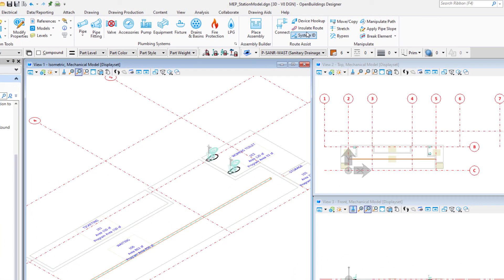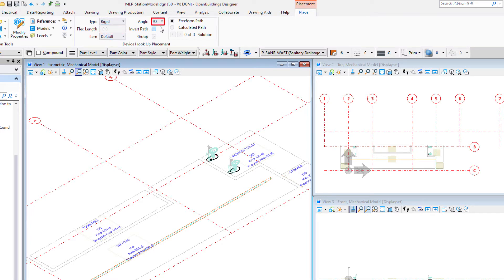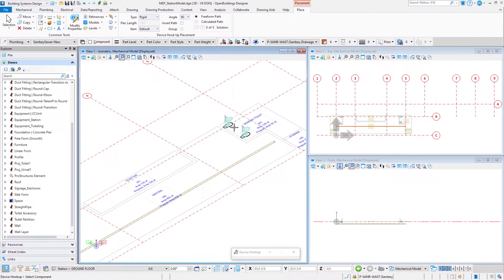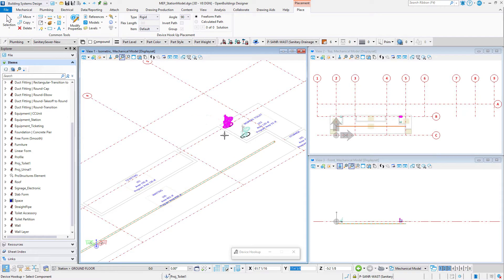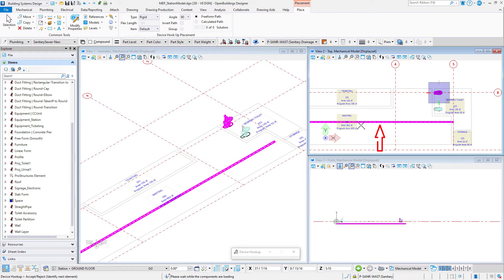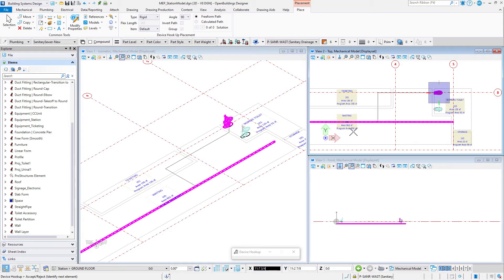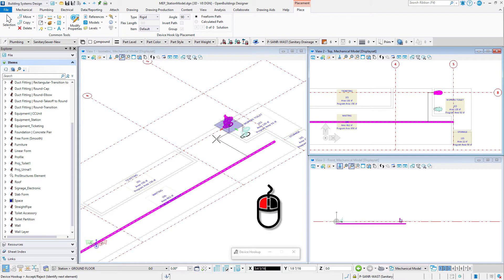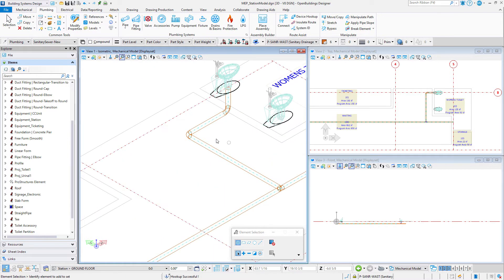Select the device hookup tool from the route assist group on the plumbing tab. On the placement ribbon, toggle on freeform path and set the type to rigid, the item to default, and the angle to 90. Then select the first toilet near its sanitary connection, which would basically be at the base of the toilet. Then select the pipe. A freeform path will appear. You can move the cursor to adjust the path so that it is outside the women's toilet room. Select the toilet, then data point to accept. A route pipe is placed connecting the toilet to the main sewer pipe. Elbows and fittings were added as needed.